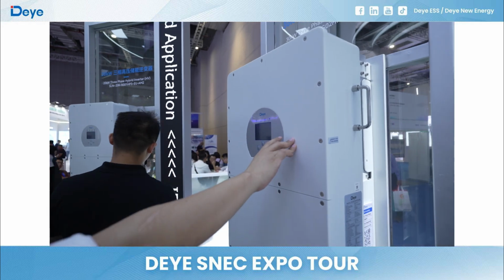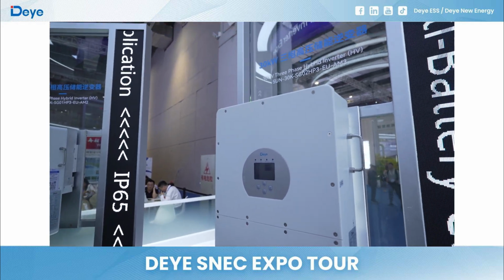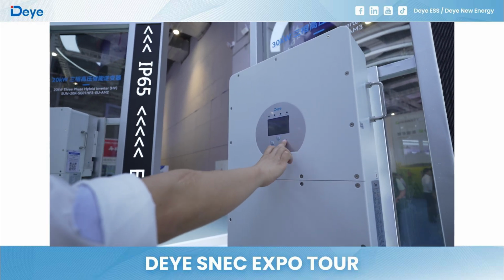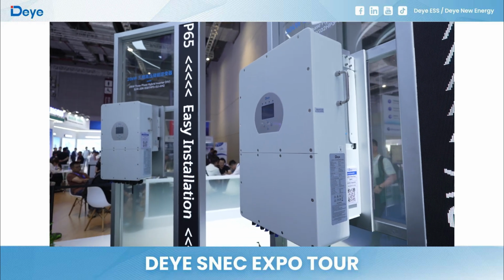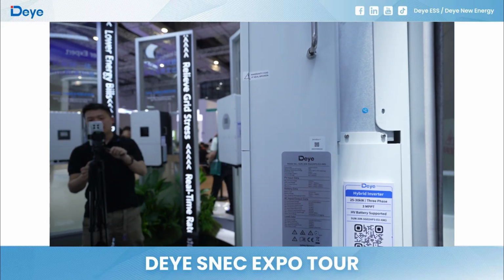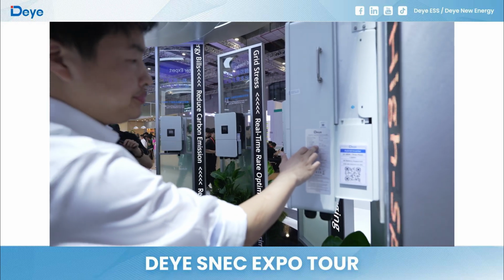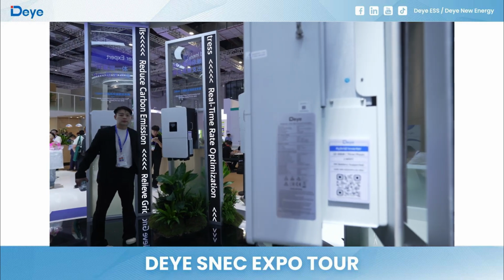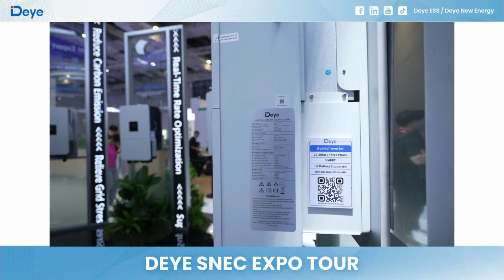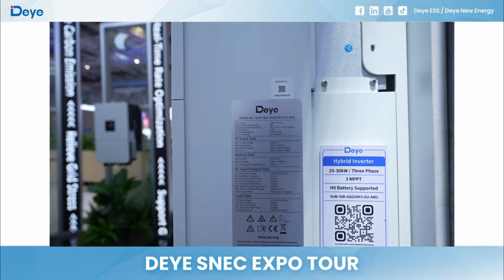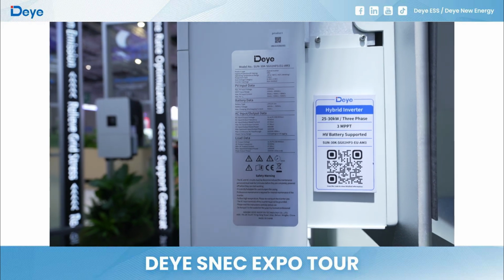And let's see this one. This one is the 3-phase 30 kilowatt hybrid inverter. Also, it has a screw on the front side, a colorful touch LCD, 4 buttons and the indicators. We can see the detailed information here. This one has 3 MPPT. Each MPPT has 2 strings. Each string current is 18 amps. It's very big. It's suited for 700 watt solar panels. And the battery charging and discharging current is 75 amps.